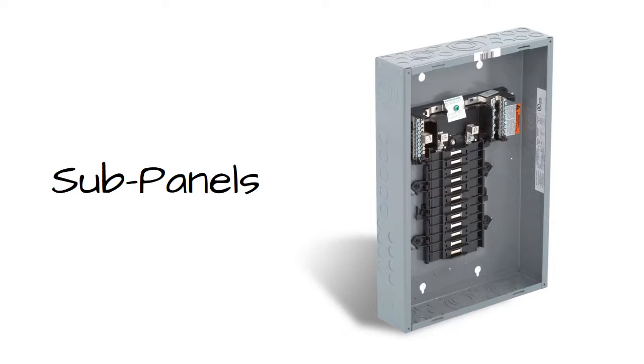To connect the sub-panel to the main panel, a connection is made through a breaker from the main panel. Null and earth are also connected back to the main panel. If there is L2, this also would connect to L2 back in the main panel. It's not necessary to have L1 and L2 in a sub-panel. However, in either scenario, the electrician should consider load balancing L1 and L2 back in the main panel.